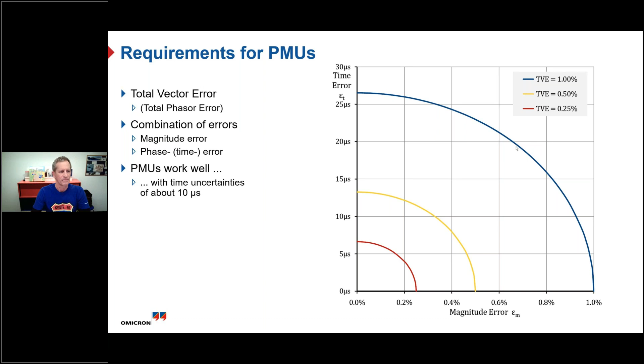To standardize this even further, the electrical power community has produced its own PTP profiles. One of them is IEC 61850-9-3, we call it the power utility profile. The goal of this profile is to stay close to the standard profile. It should be possible to utilize a standard clock to tune the parameters and make it then working as specified in this profile. It's also called the basic profile. And the IEEE profile, the old power profile, which came first, is now seen as the advanced profile. But the use cases are well served with the basic profile, as we call it, 9-3.